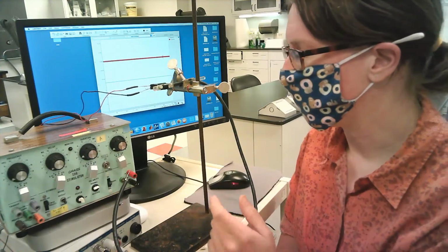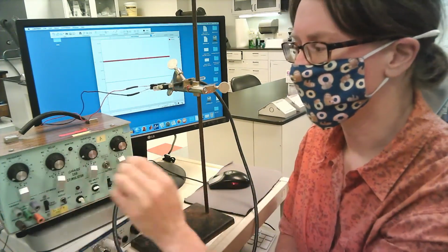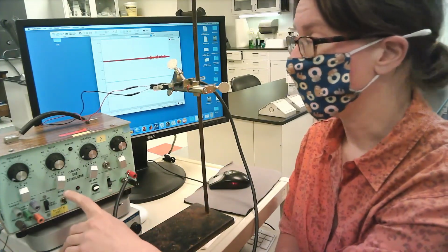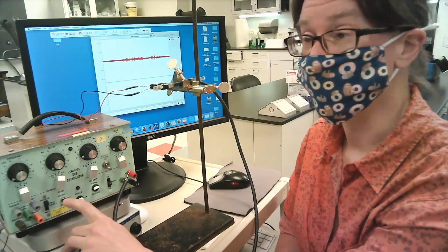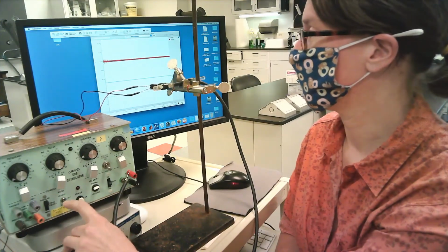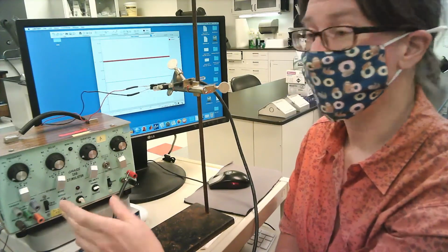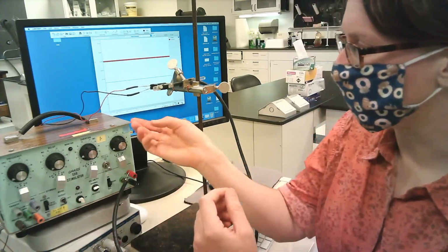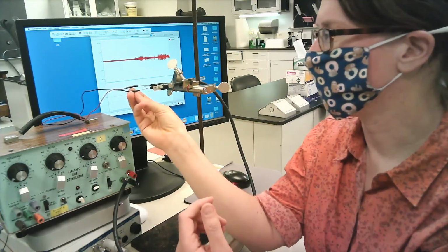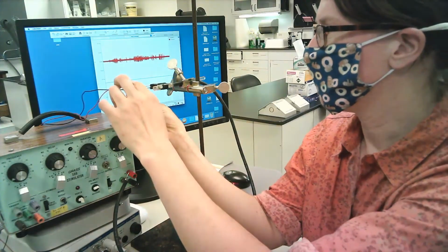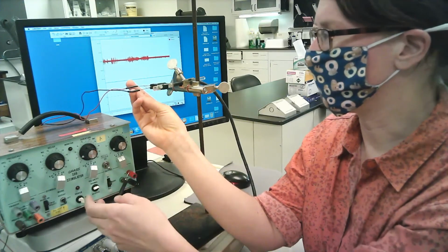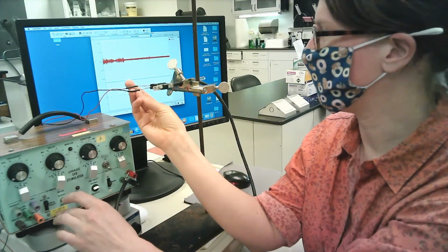So now I've got Chart running. I've got my initial conditions set where I want them. To just do a single test, I'm going to use this mode toggle switch here. If I press down once, that will deliver a single stimulus. Okay, and it's not showing me anything on Chart. So that suggests to me that I might have a contact that's not complete at the moment. As you can see, there's some background voltage here, even when I'm not delivering a stimulus. So now I'm going to try repeating that.